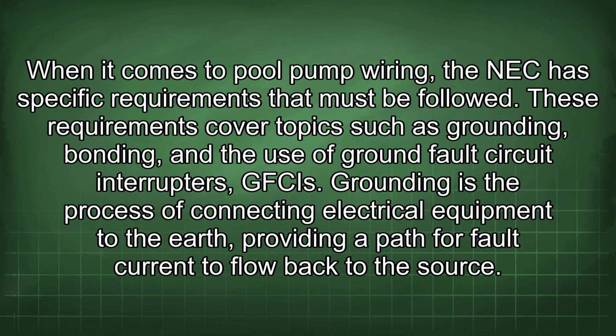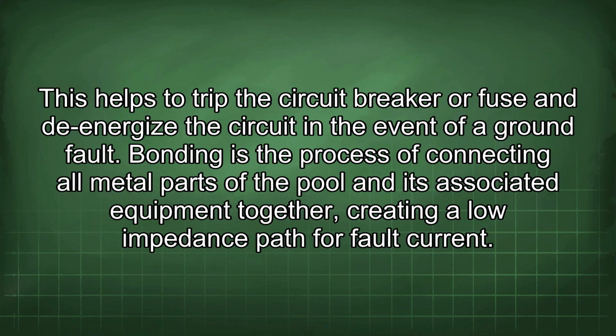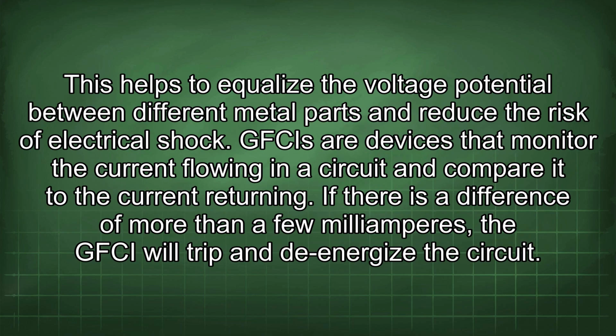When it comes to pool pump wiring, the NEC has specific requirements that must be followed. These requirements cover topics such as grounding, bonding, and the use of ground fault circuit interrupters, GFCIs. Grounding is the process of connecting electrical equipment to the earth, providing a path for fault current to flow back to the source. This helps to trip the circuit breaker or fuse and de-energize the circuit in the event of a ground fault. Bonding is the process of connecting all metal parts of the pool and its associated equipment together, creating a low impedance path for fault current. This helps to equalize the voltage potential between different metal parts and reduce the risk of electrical shock.